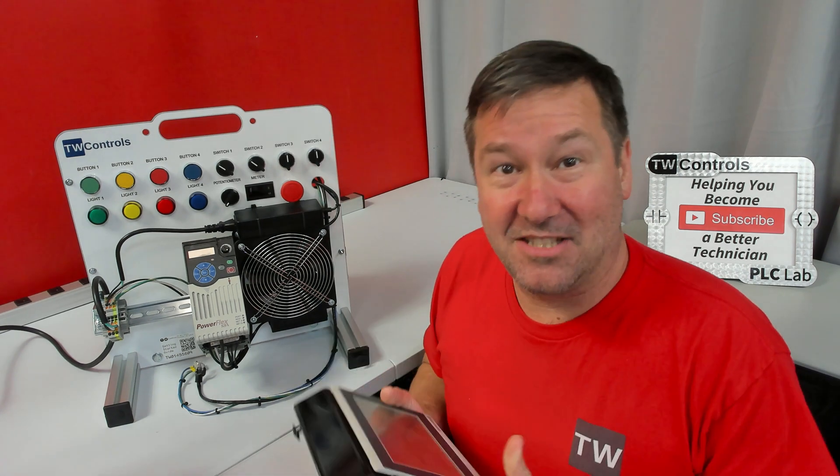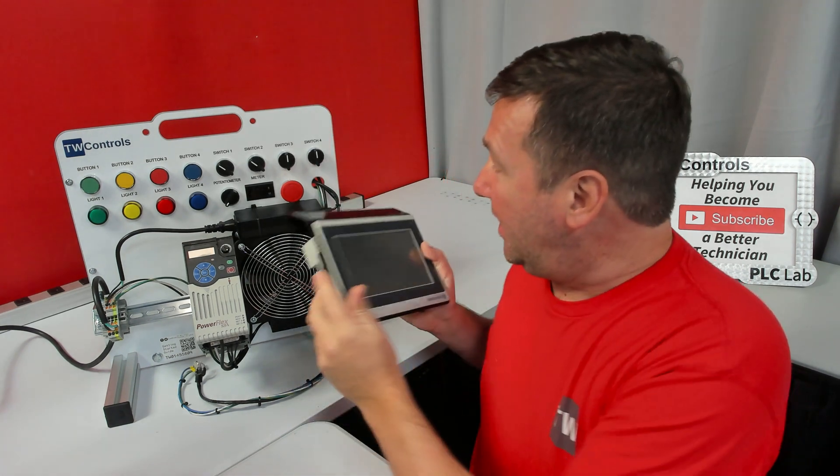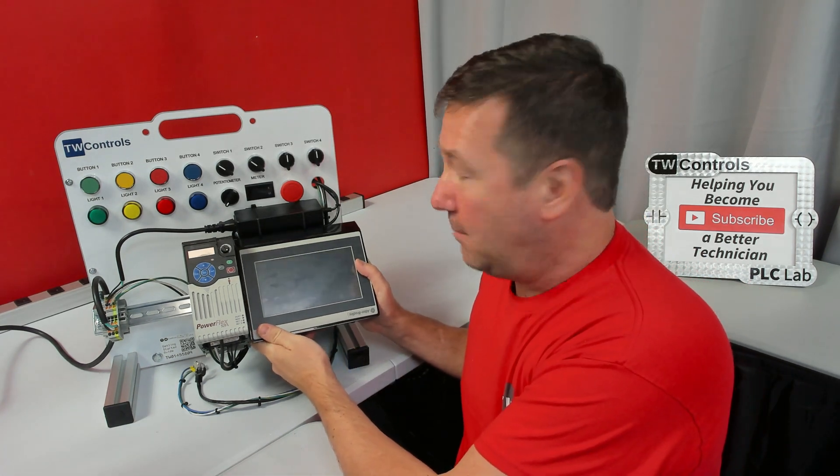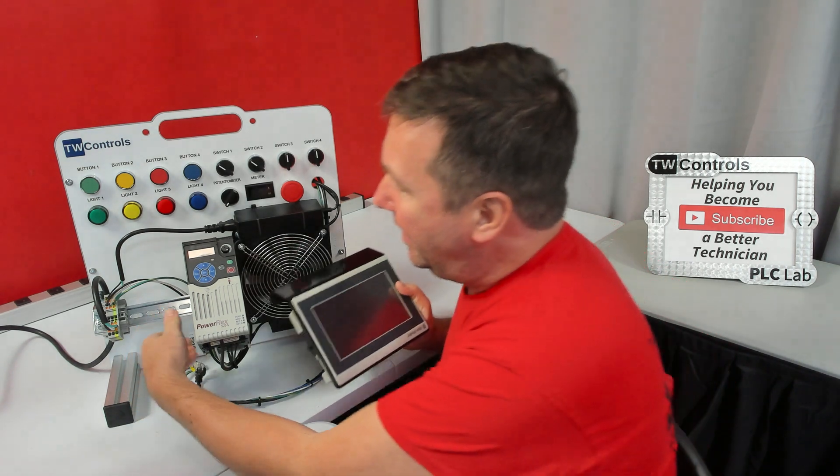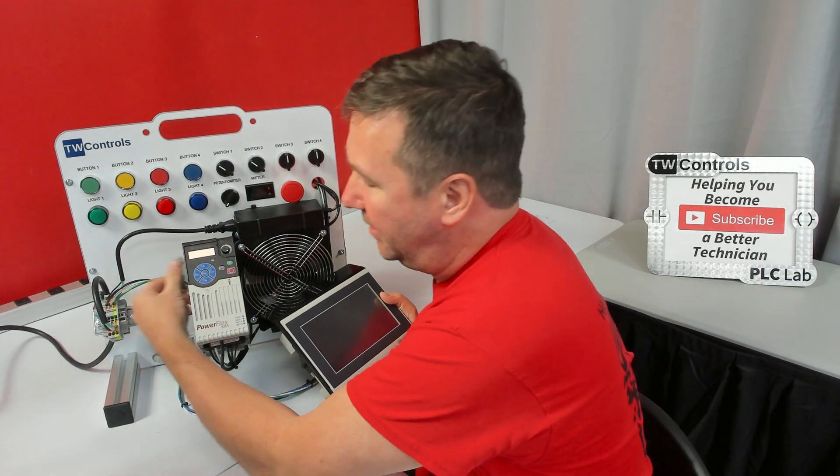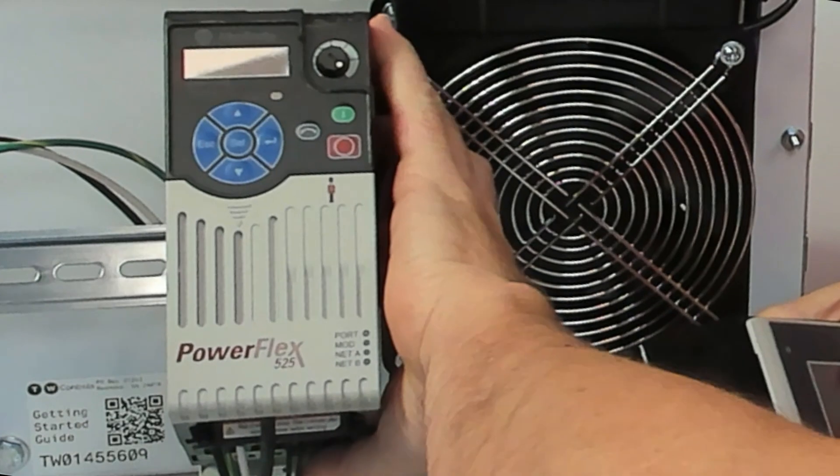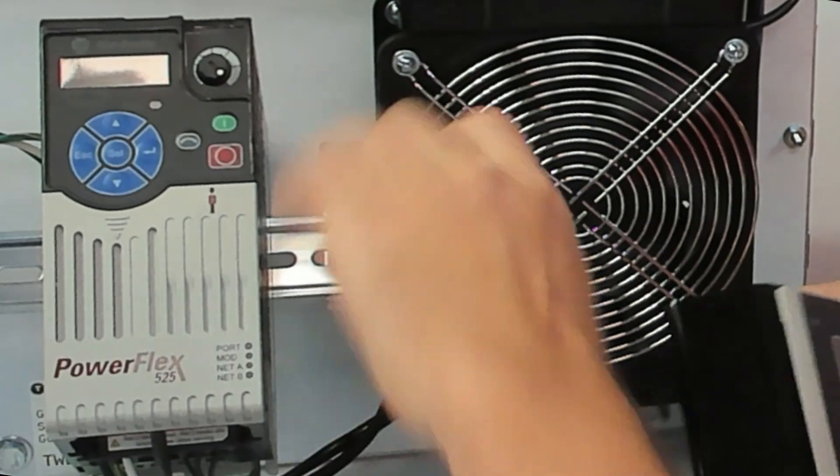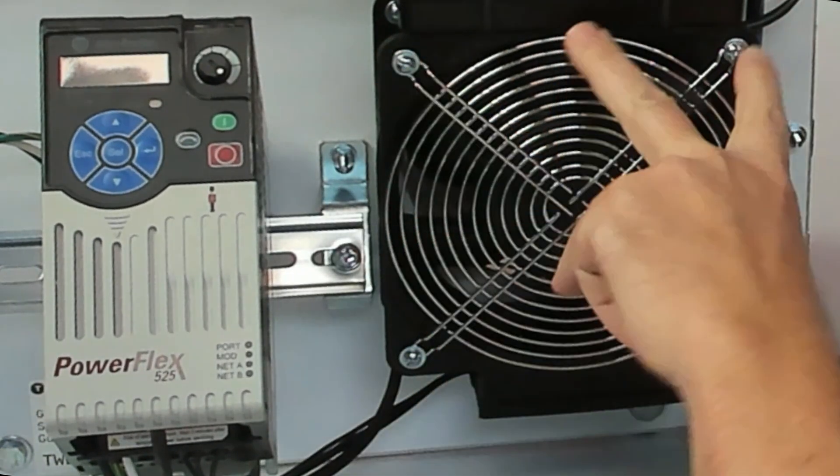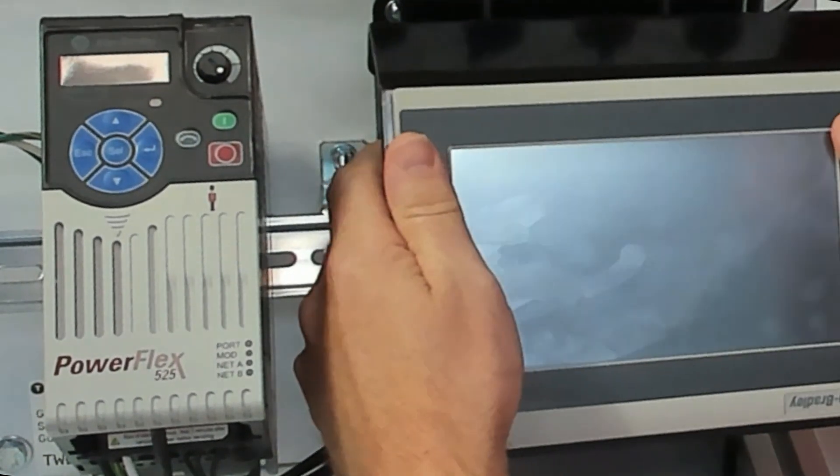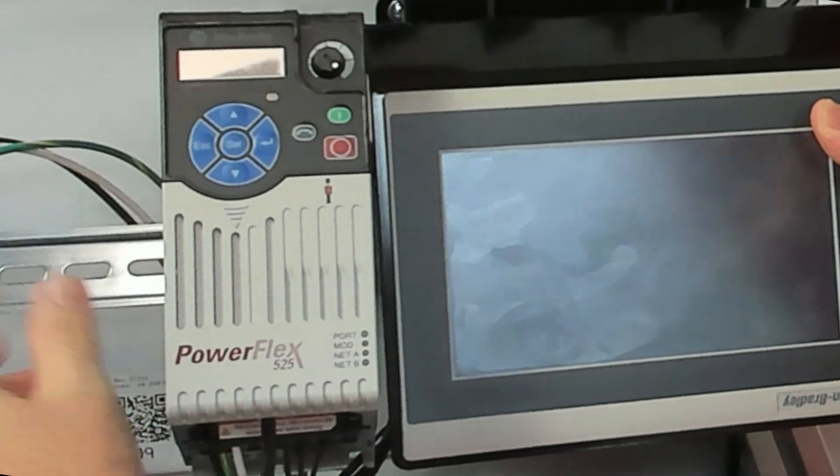The HMI has two mounting opportunities. It has the front mount for a compact application, and in that case, we're going to pop the end anchor off the left side of the PowerFlex drive, slide the PowerFlex over. You'd remove these two screws, put this in place, reinstall the screws, slide this to the left, and reinstall the end anchor.